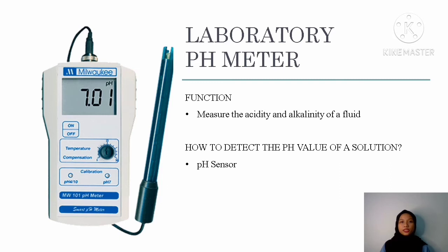The laboratory equipment that we'll talk about today is the laboratory pH meter. The function of the device is to measure the acidity and alkalinity of a fluid. The meter usually has two types of electrode. The first one is a pair of electrodes, which consists of a glass electrode and a reference electrode. The second one is a combination electrode.